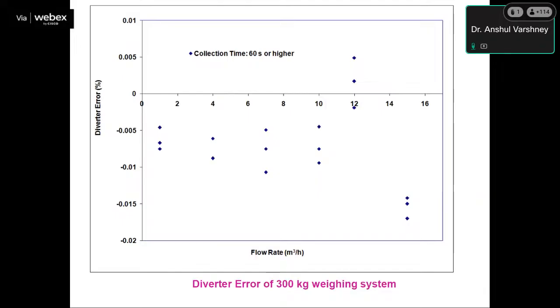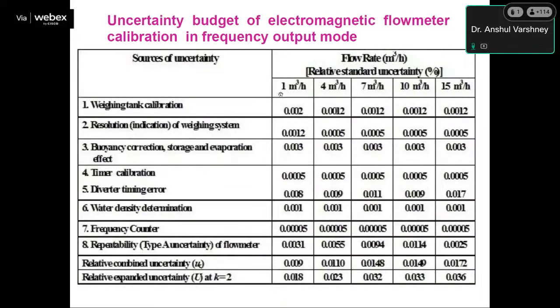But this is basically the percentage diverter error of the 300 kg weighing system for different flow rates. Our diverter error is quite small. The sources of uncertainty for electromagnetic flow calibration in frequency mode are weighing tank calibration, resolution of weighing scale, buoyancy correction, timer calibration, diverter error, water density, frequency counter, and repeatability.